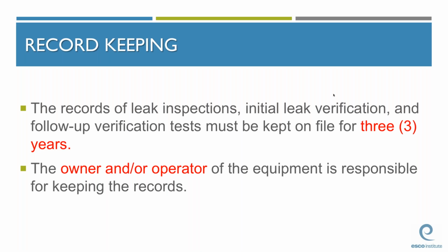And one of the reasons for the owner-operator having to keep these records is there might be more than one company servicing the equipment. So if the service company is responsible for maintaining these records, they will only know and have records of the work they performed. So their leak test or their leak rate calculations might not be accurate if they're not taking into account refrigerant that was added to the system by other contractors.